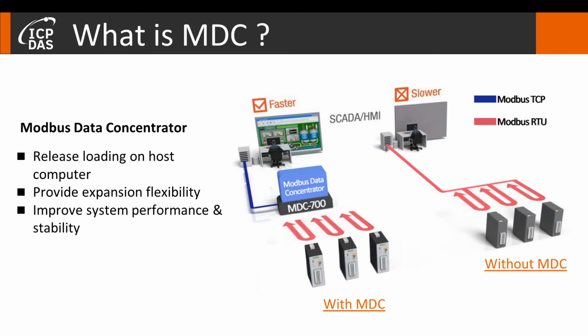So what is MDC? MDC means Modbus Data Concentrator. It can release the loading on the host computer by helping it collect data from different devices and send all the data back to the computer together. And MDC provides expansion flexibility. When there are more and more connected devices and data to collect, you don't have to worry that your host computer will be overwhelmed with the large amount of data. The only thing you need to do is add an MDC. It can help you collect the mass amount of data. In this way, MDC improves system performance and stability, as you can see in the left picture.